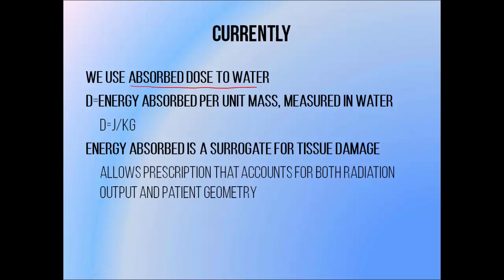At the moment we use absorbed dose to water, which is defined in terms of joules per kilogram. It's the amount of energy absorbed per unit mass of material. We normally perform our absolute dose measurements in terms of grey in water, because of convenience and the fact that it has similar radiation interaction properties to human soft tissue. The 'to water' part of absorbed dose to water is a lot more confusing than it really needs to be - I'm going to cover it in more detail in a future tutorial - but suffice to say for now that it's a measurement of energy absorbed per unit mass of water measured in a water phantom. We use it as a surrogate for tissue damage, so more dose generally means more ionization in a tissue and therefore more damage. This allows us to determine dose inside a patient, independent of the machine that's used to deliver it, and the geometry of the patient too.